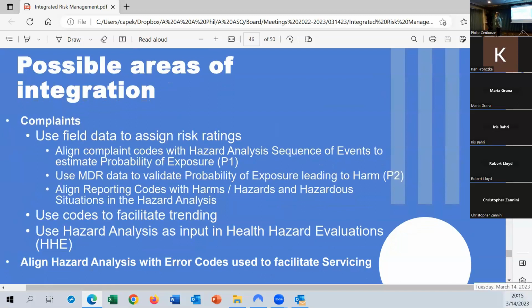Other things that you can do with the risk document: you can actually use field data to assign the probability, like P1. So if you have a granular enough, detailed sequence of events and your complaint handling analyzes to root cause, you can map those so that I can take field data and estimate P1. It is the expectation of FDA that you are using field data at least to help you determine what P1 is. So purely quantitative P1 is hard to do. You have to have a really good description of complaints that most people don't have, but at least semi-quantitative, where you're analyzing that data and then using your expert judgment, or your best judgment, on what that P1 should be.